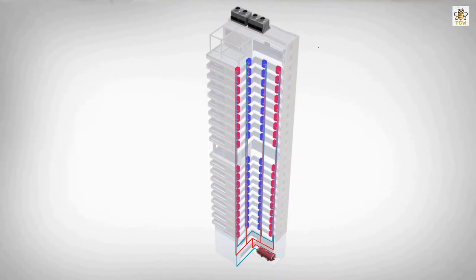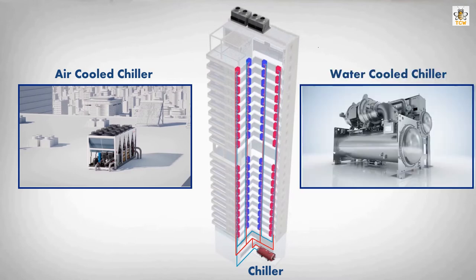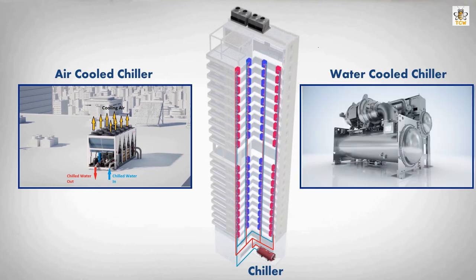The chiller is the equipment used to produce chilled water, which is flowed to the air handling unit. There are two types of chiller: air-cooled chiller and water-cooled chiller. An air-cooled chiller removes heat from the chilled water using outdoor air directly and is usually placed at the top of the building. A water-cooled chiller uses another water called condenser water to remove heat from the chilled water, and is usually placed at the basement. In this video, we are using a water chiller as an example.